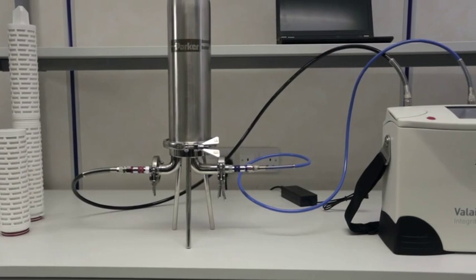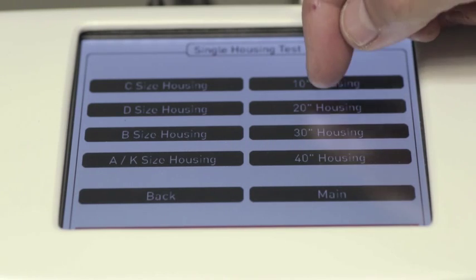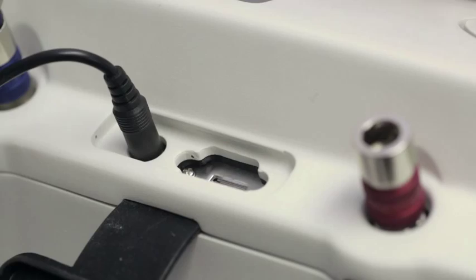The test takes seconds to perform, with a typical 10-inch filter system taking just 30 seconds to complete.